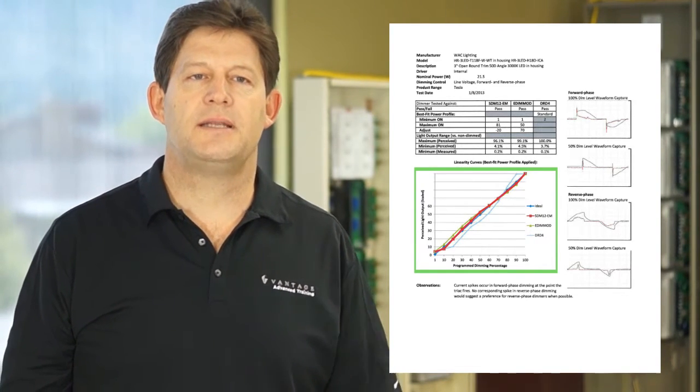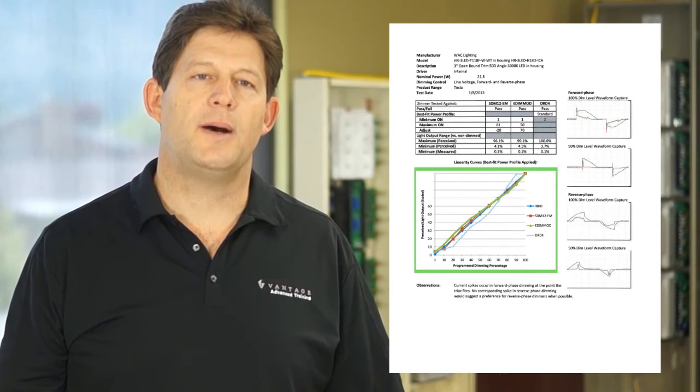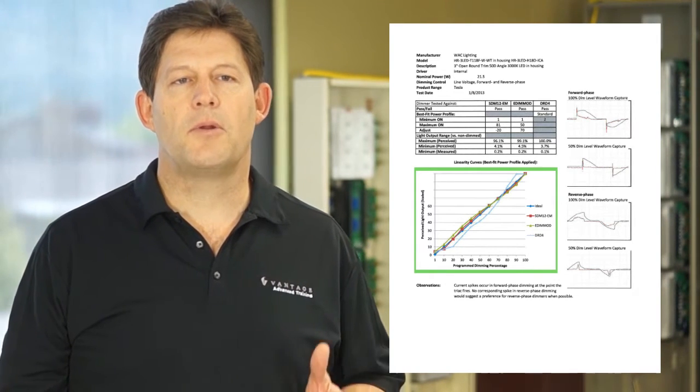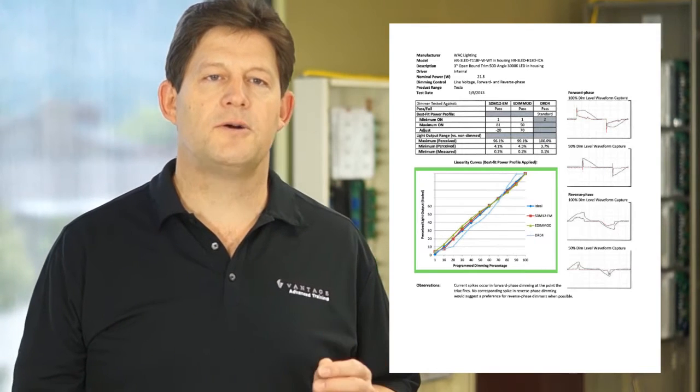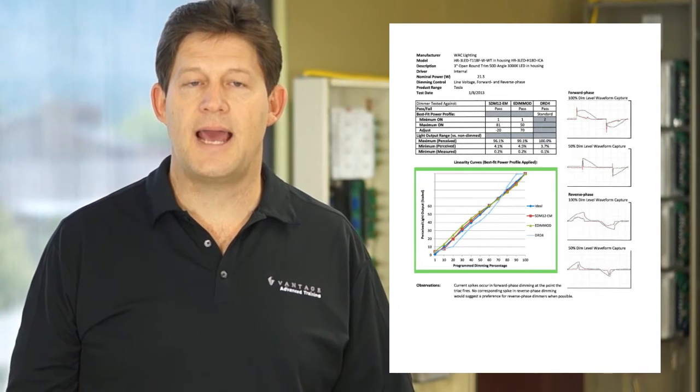The red line represents the standard dimmer module, the green line the electronic dimmer module, and the light blue the DRD4. You can see in this particular report that both native Vantage dimmer curves follow the ideal very, very closely. Your eye would likely not be able to detect that these don't follow the ideal exactly.